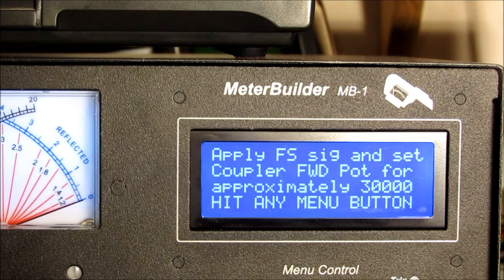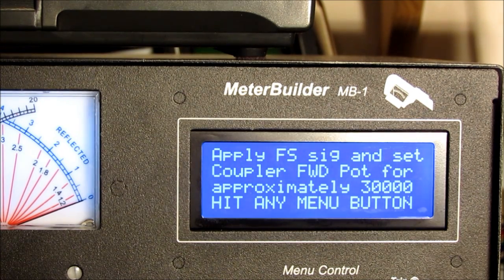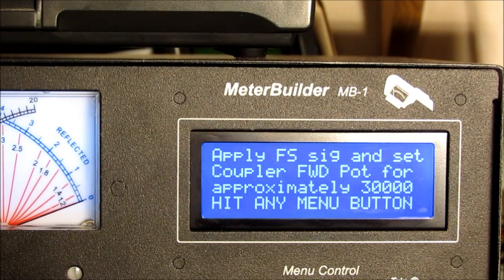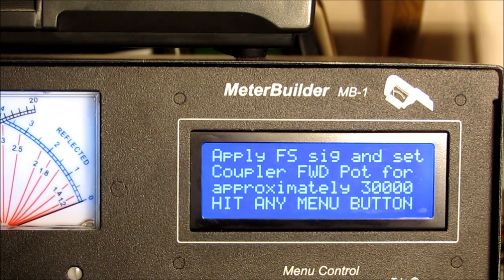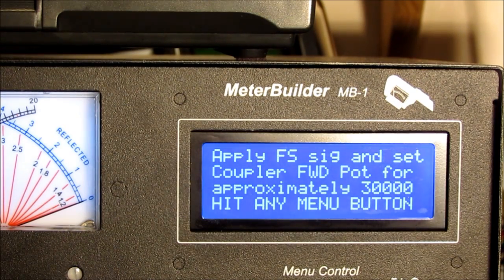The meter is now prompting us to set the forward trim pot. With 15 bits of resolution, the analog to digital chain has a maximum output of approximately 32,768. We don't want to overdrive the front end system, so we're prompted to apply the full scale power we're interested in calibrating the coupler at, then adjust the trim pot to get close to the maximum value without overdriving the analog to digital converter. We want maximum resolution and accuracy, but we don't want to top out.